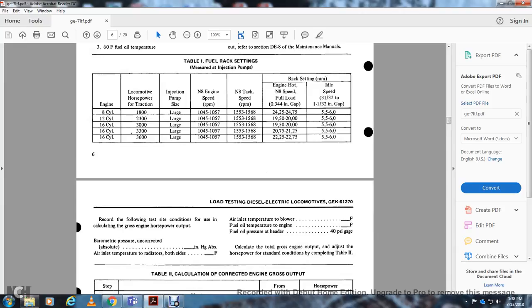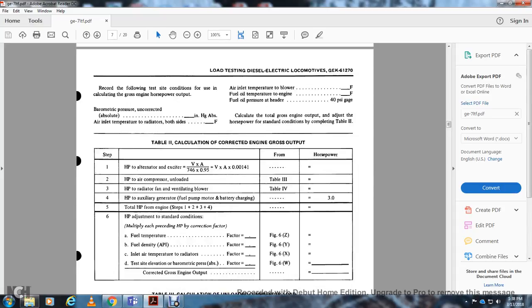Record the following tests and conditions for calculating gross engine horsepower: barometric uncorrected, air in temperature for the radiator on both sides, and air in temperature for the blower, fuel oil temperature, all in Fahrenheit, and fuel oil pressure at the header, 40 psi. Calculate the total gross engine output of the jet for the horsepower standard conditions. Complete table 2.